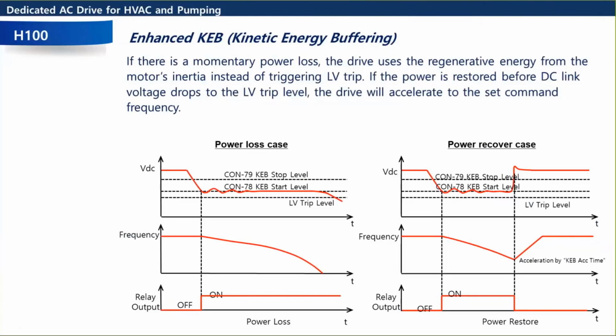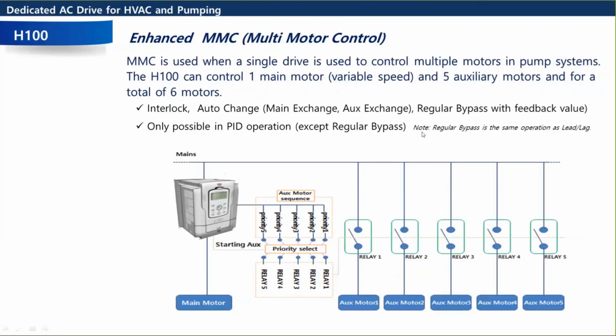Okay, and then if the power ever comes back, the drive's going to try to start back up. So this is what KEB is, and that's kind of what they're showing here. Your voltage drops. There's your low voltage level trip here, but instead of hitting that low voltage level trip, you hit this start level for KEB, and that tries to keep your DC voltage stable. Okay, so you have somewhat stable bus capacitors on there. And then if the power ever came back, you'd see it just come back on like normal, uninterrupted, just a way to eliminate a trip.